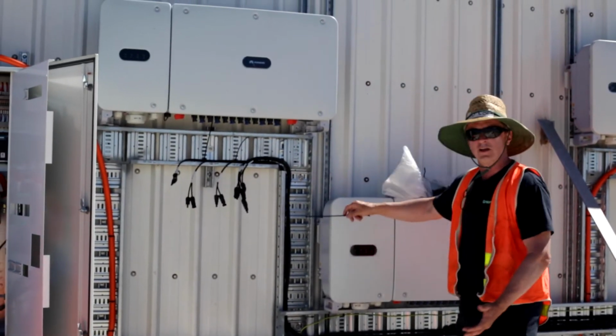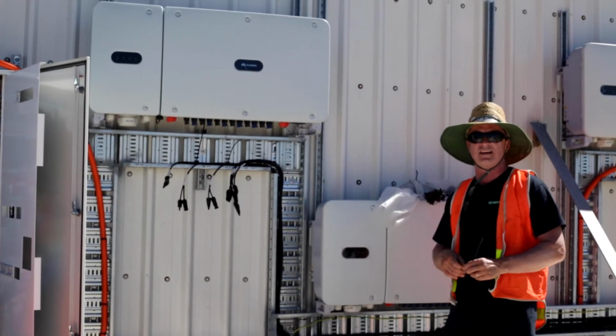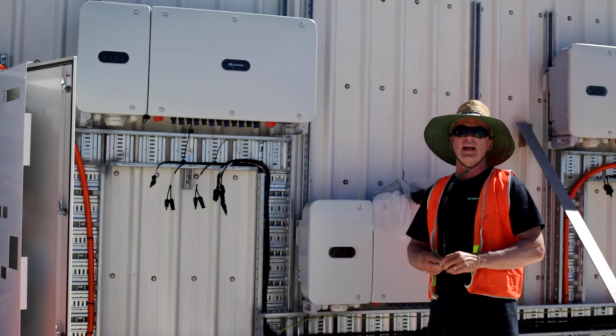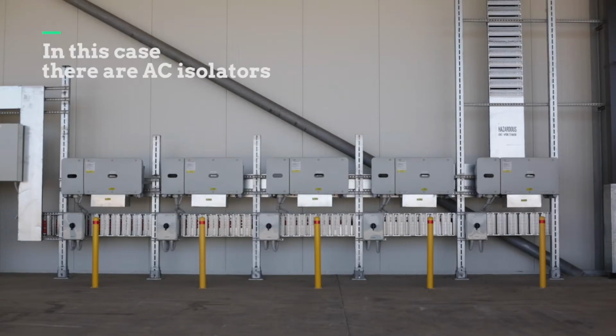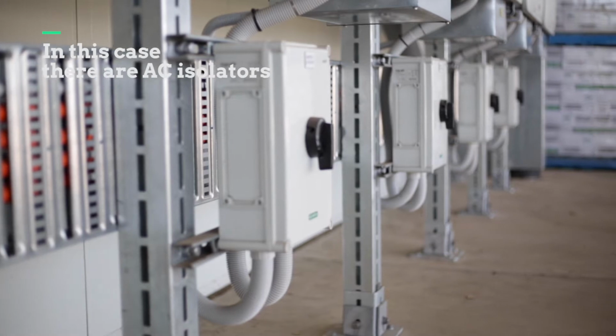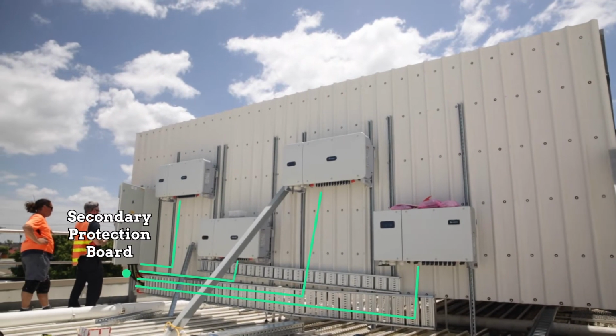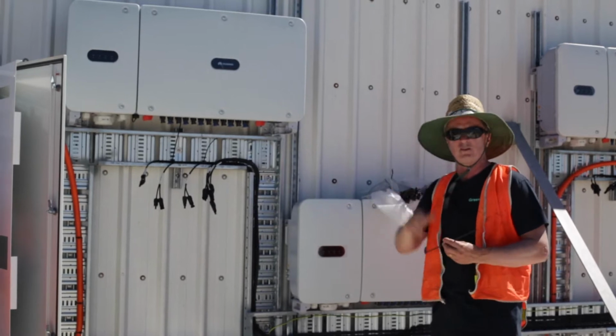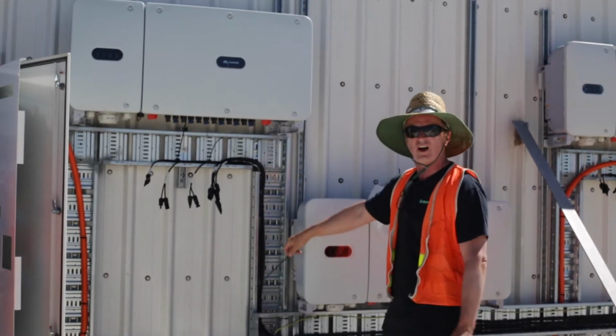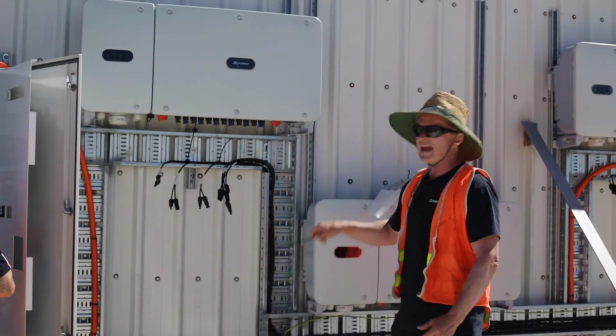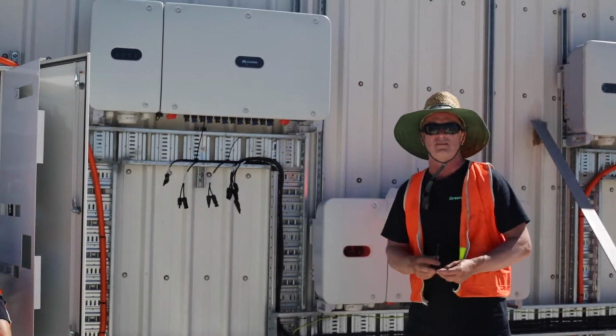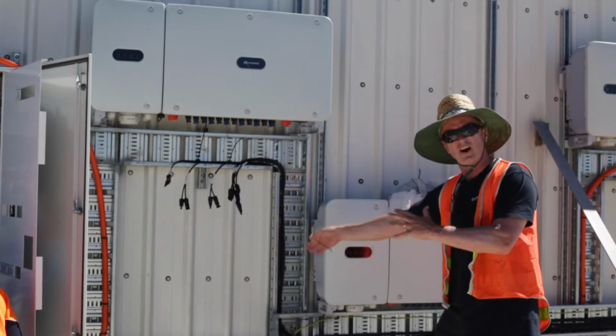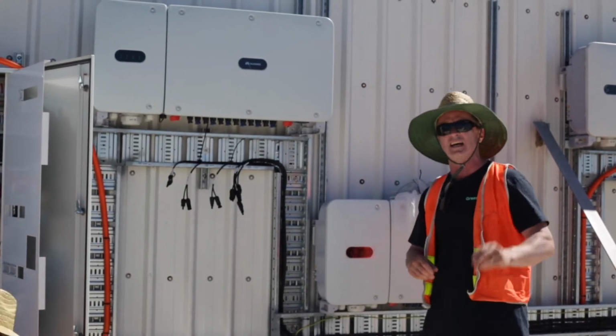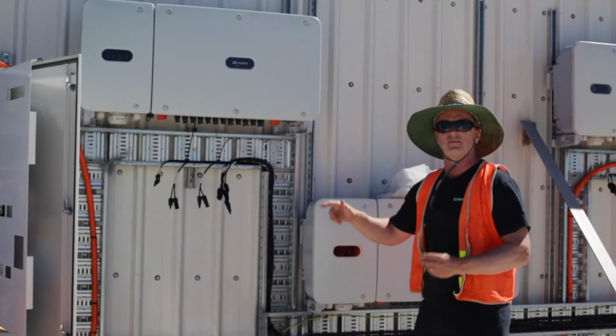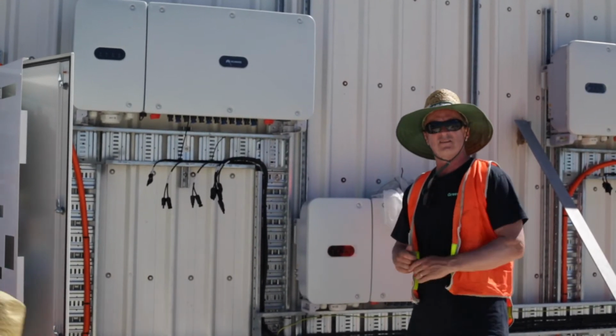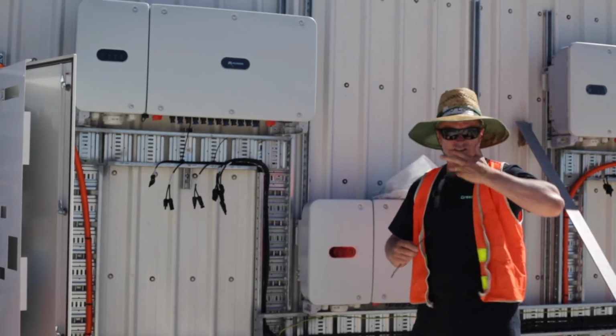Now, you may notice in this situation there is no specific AC isolators, and that is because of the proximity of these inverters to the actual secondary protection board. If this secondary protection board was out of sight or many meters away, you would have individual AC isolators then connecting to the circuit breakers. If we did have isolators here, you can't have an isolator connected to an isolator. There has to be a circuit breaker in that particular circuit. So isolator to circuit breaker.